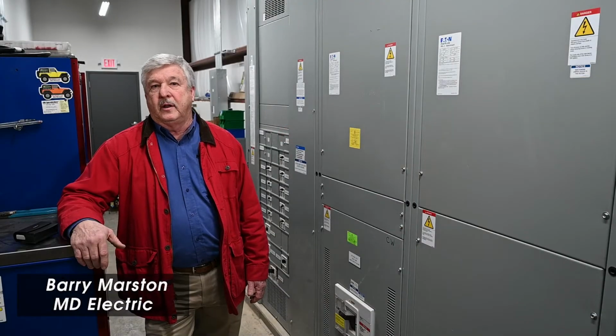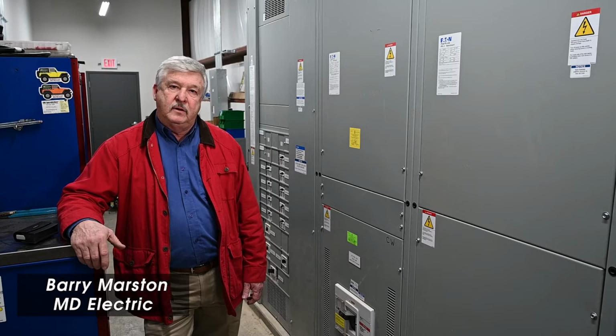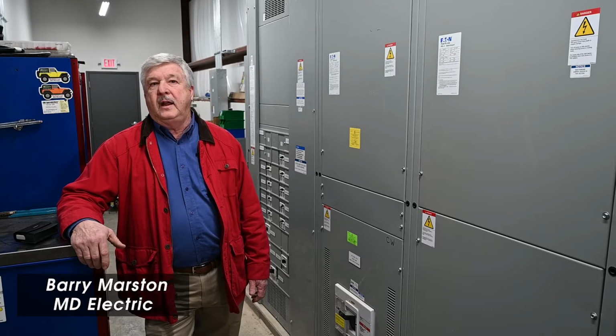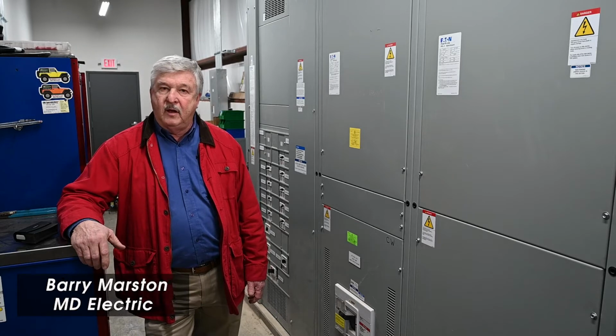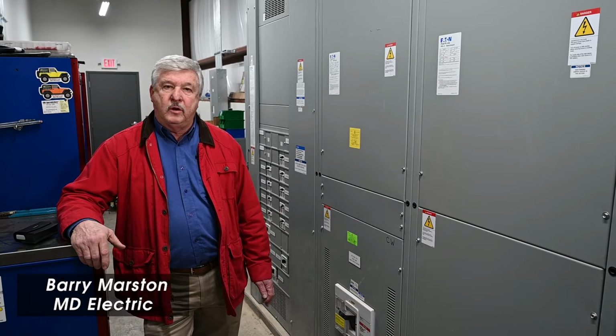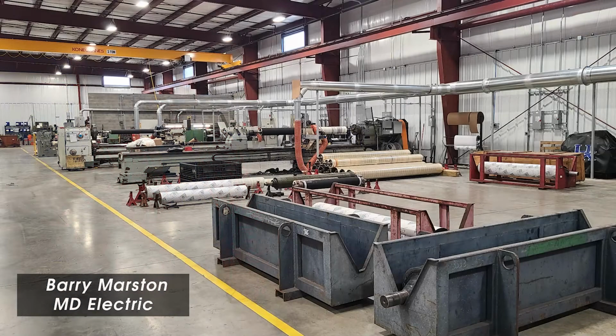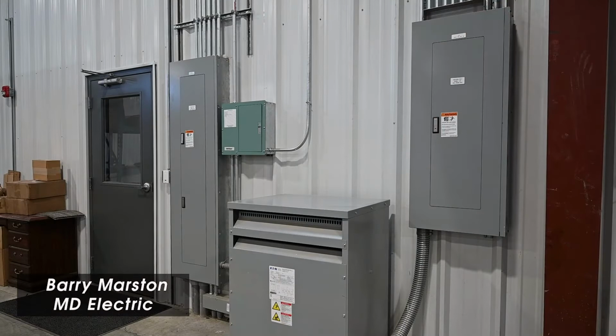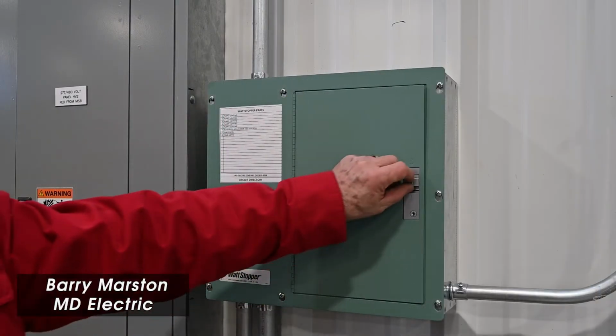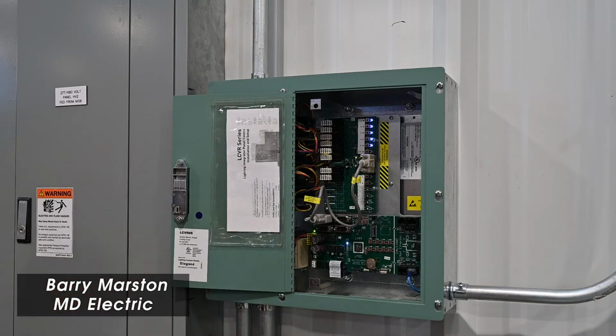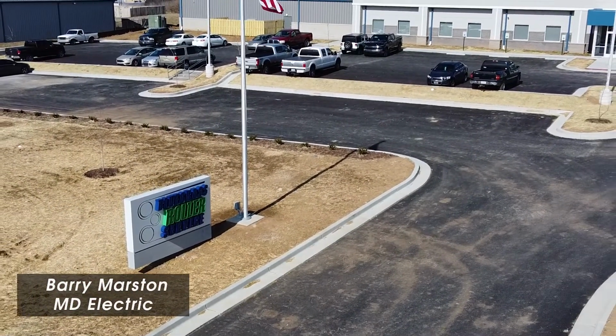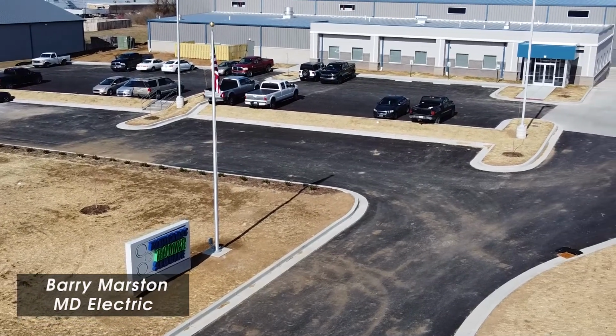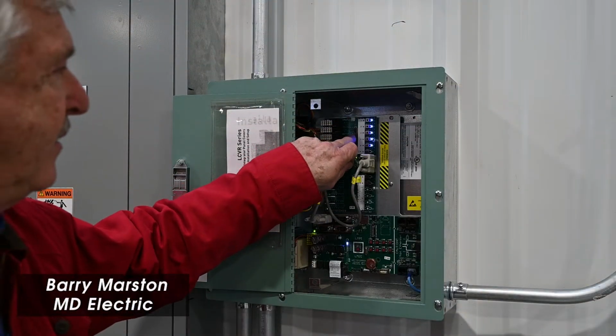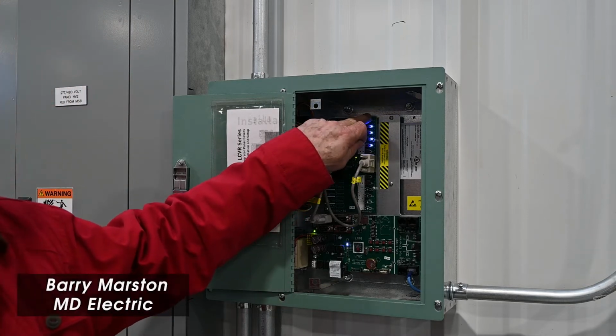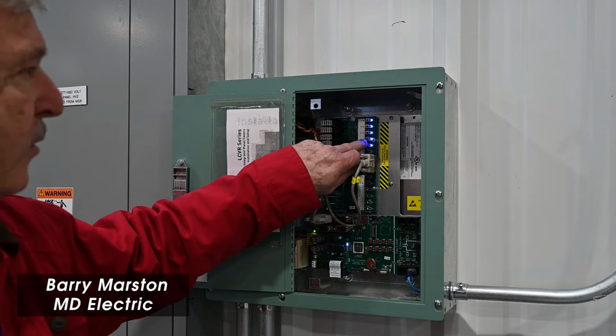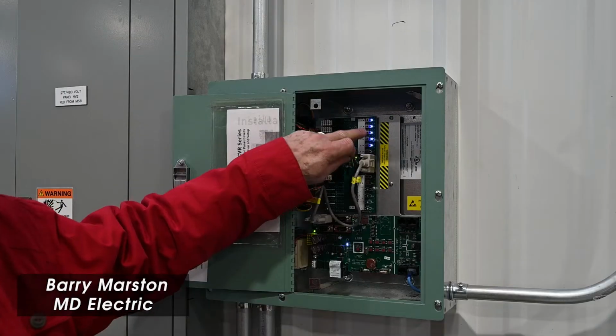This setup occurs in 3 other places. We have HV2, LV2, HV3, LV3, and HV4 and LV4. All 480 volt and 120 volt, 208 volt, 3-phase for their equipment. We have a panel beside HV2 that is a Watt Stopper panel, and it controls the plant lighting as well as their sign, flagpole, and site lighting and wall packs on the building. All are labeled to designate what they turn on and off, and there are switches at each door as you come in to the plant to turn off the lighting for the plant.